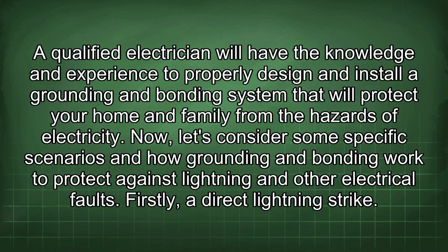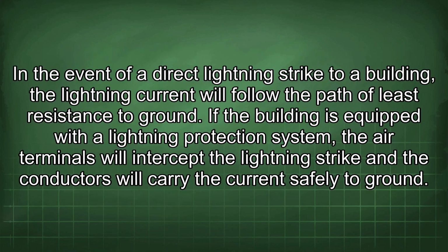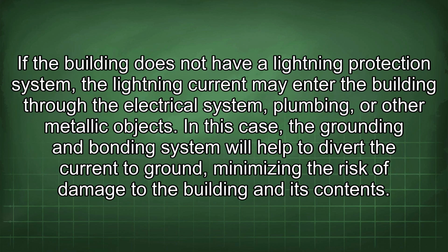Now let's consider some specific scenarios and how grounding and bonding work to protect against lightning and other electrical faults. Firstly, a direct lightning strike. In the event of a direct lightning strike to a building, the lightning current will follow the path of least resistance to ground. If the building is equipped with a lightning protection system, the air terminals will intercept the lightning strike and the conductors will carry the current safely to ground. If the building does not have a lightning protection system, the lightning current may enter the building through the electrical system, plumbing, or other metallic objects. In this case, the grounding and bonding system will help to divert the current to ground, minimizing the risk of damage to the building and its contents.